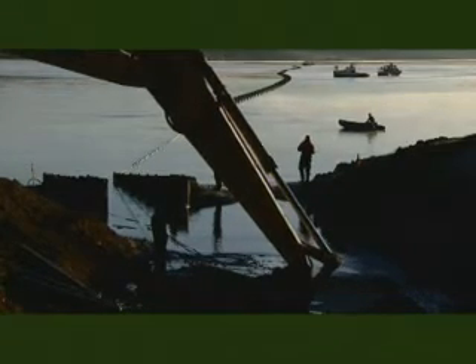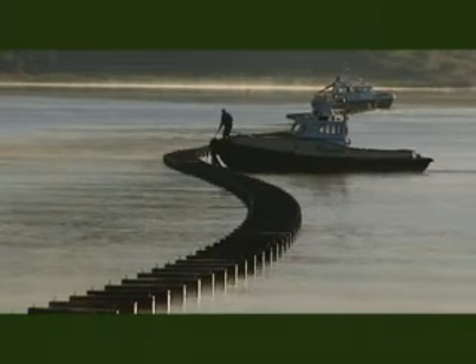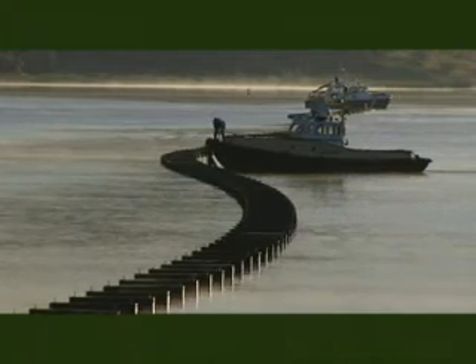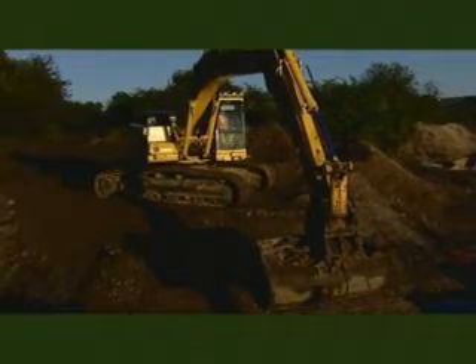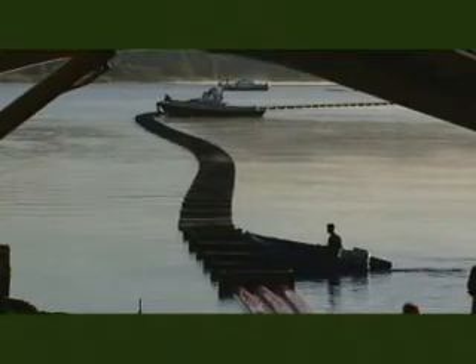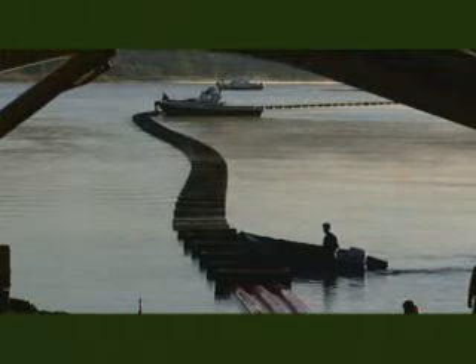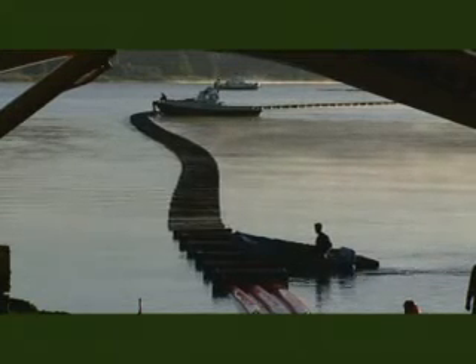This operation avoided the need for an uncertain and costly directional drilling. Also, it was possible to lay the pipes without markedly disturbing the floor of the inlet. And it was possible to draw a non-armoured submarine cable through the pipes running along the bottom of the inlet in just the same way as the cables are pulled through pipes on land. The cables had to be pulled through 700-metre-long pipes without resting on rollers.